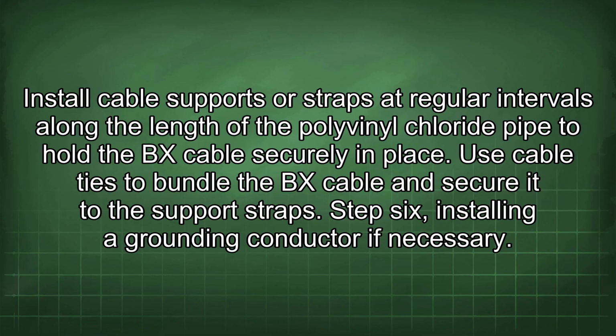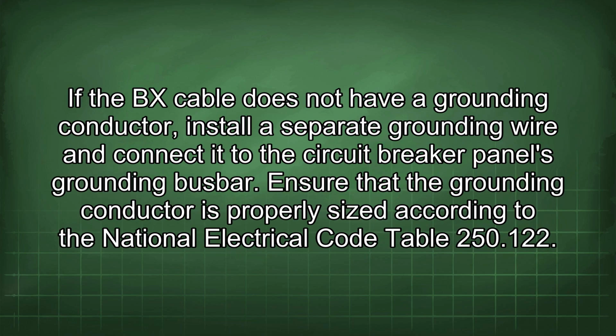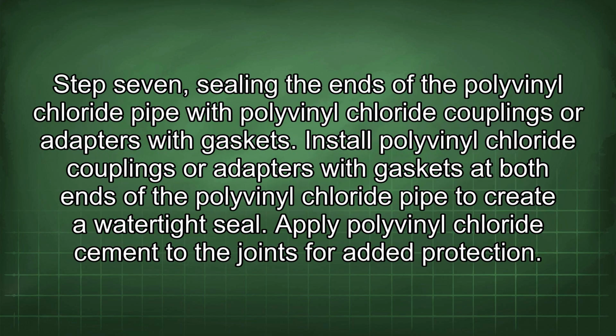Step 6. Installing a grounding conductor if necessary. If the BX cable does not have a grounding conductor, install a separate grounding wire and connect it to the circuit breaker panel's grounding busbar. Ensure that the grounding conductor is properly sized according to the National Electrical Code Table 250.122. Step 7. Sealing the ends of the polyvinyl chloride pipe with polyvinyl chloride couplings or adapters with gaskets.